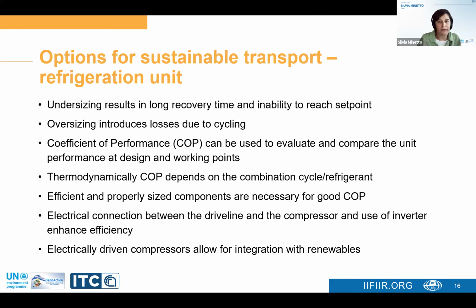Coefficient of performance is widely used in stationary refrigeration and can be a good parameter to evaluate and compare different units at fixed working points, like the design point. COP thermodynamically depends on the combination of cycle and refrigerant, but to achieve this COP we must implement efficiently and properly sized components.